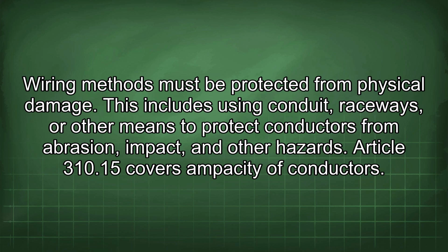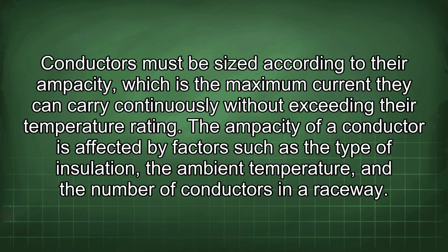Article 310.15 covers ampacity of conductors. Conductors must be sized according to their ampacity, which is the maximum current they can carry continuously without exceeding their temperature rating. The ampacity of a conductor is affected by factors such as the type of insulation, the ambient temperature, and the number of conductors in a raceway.